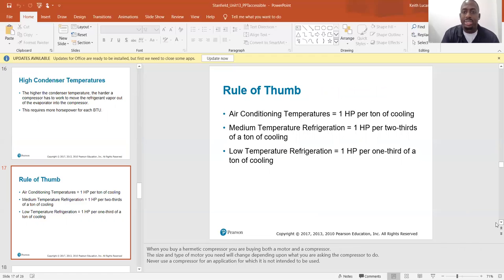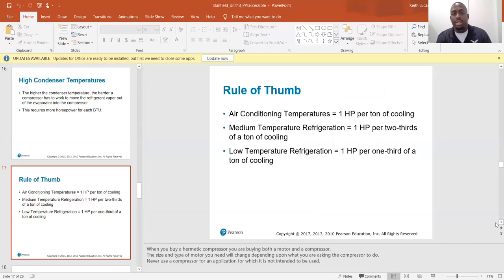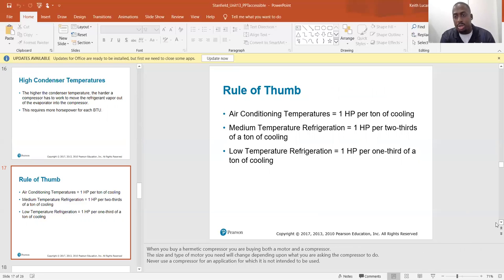Rule of thumb: air conditioning temperatures equal one horsepower per ton of cooling. Medium temp refrigeration equals one horsepower per two-thirds of a ton of cooling. Low temp refrigeration equals one horsepower per one-third of a ton of cooling.